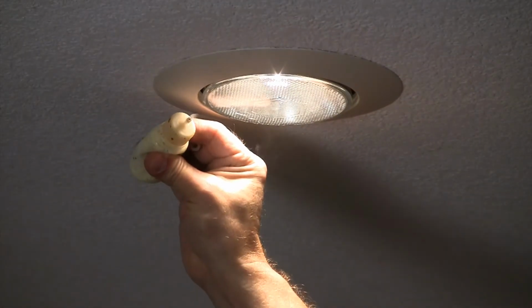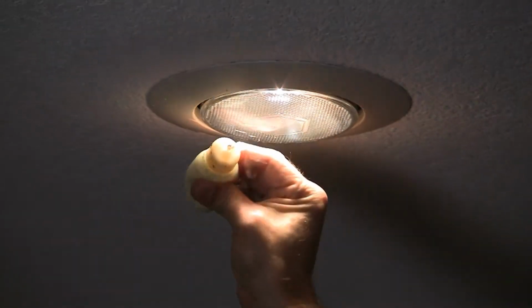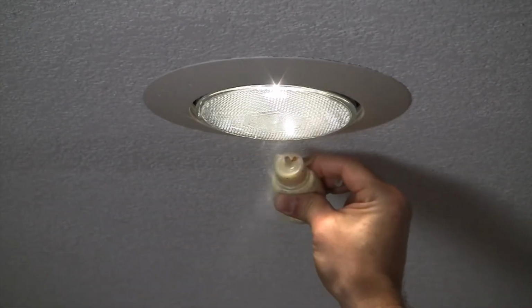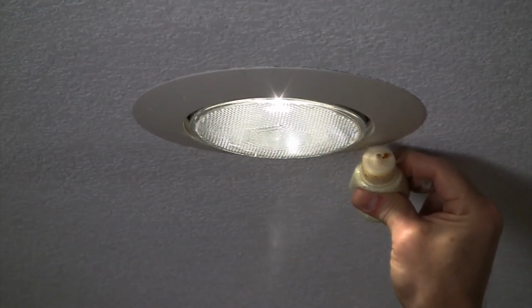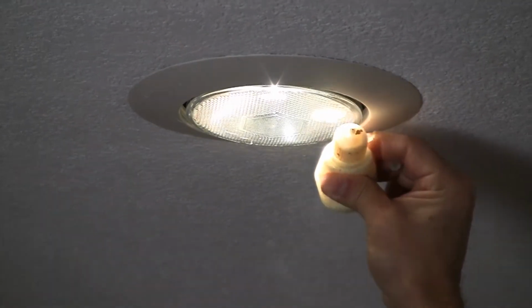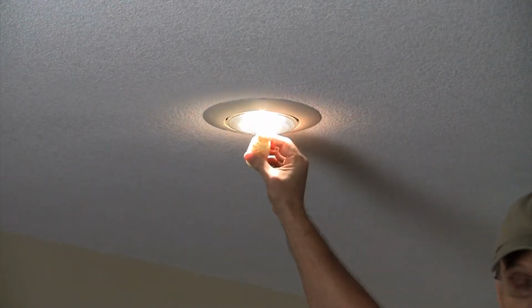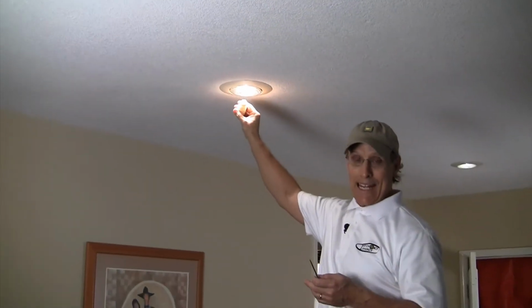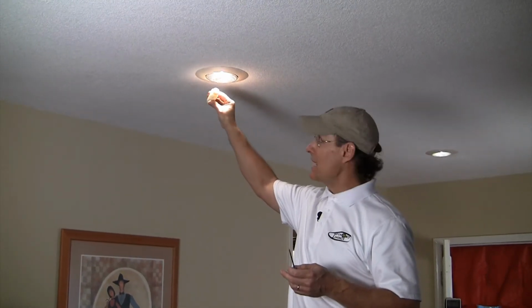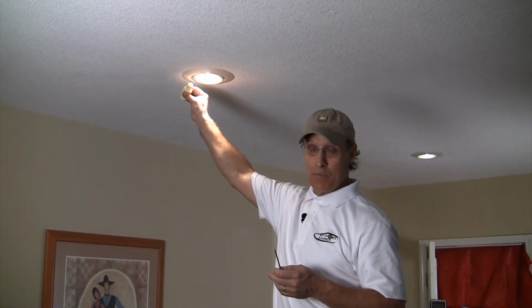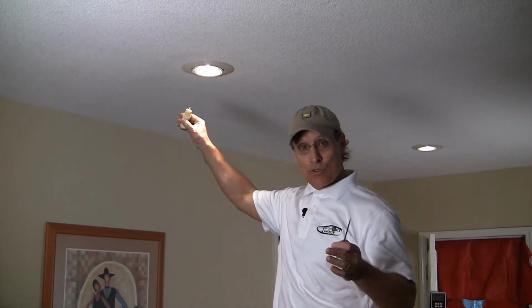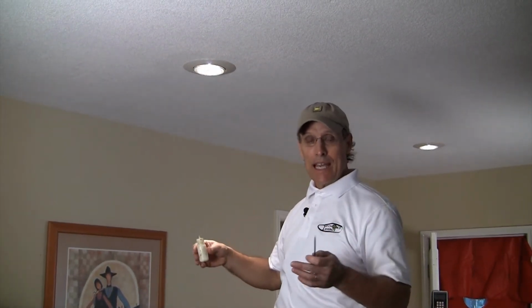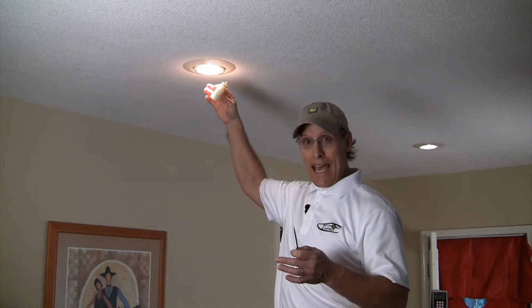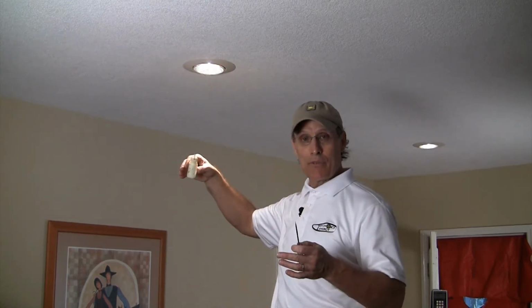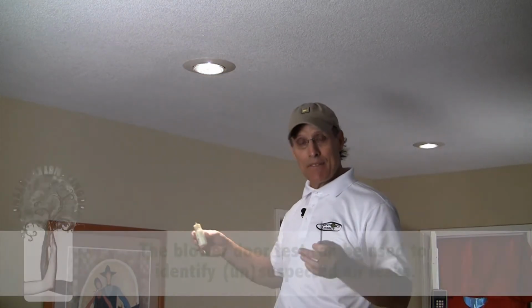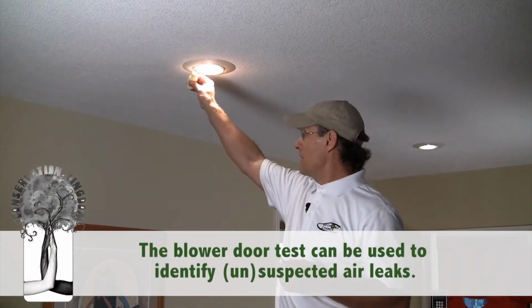You can see I'm generating smoke, and see how the smoke is just pouring out of this recessed light fixture. Just very, very leaky. And that's basically sucking in outside air and attic temperature air. So in Austin, Texas, that can be 150-degree air that is being sucked into your house on a natural basis every day. As your house is breathing, you're getting attic air coming in through the recessed lights, and now you're having to condition that. So very important.